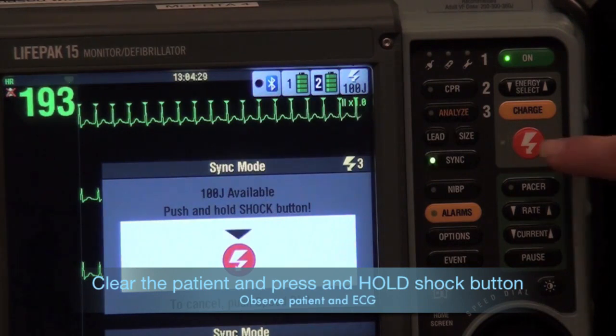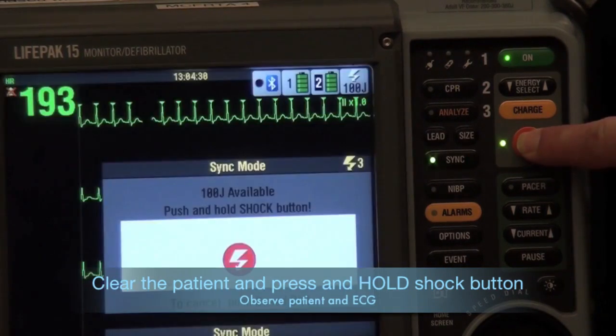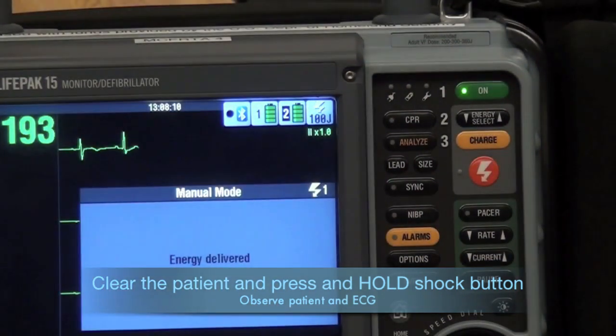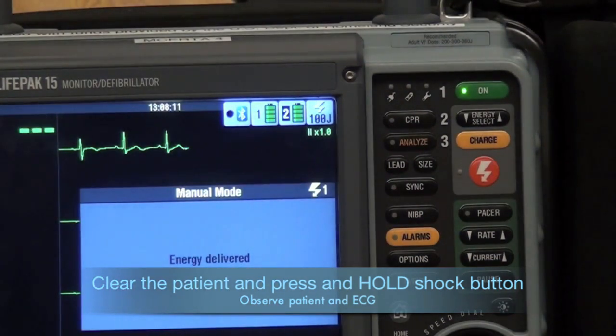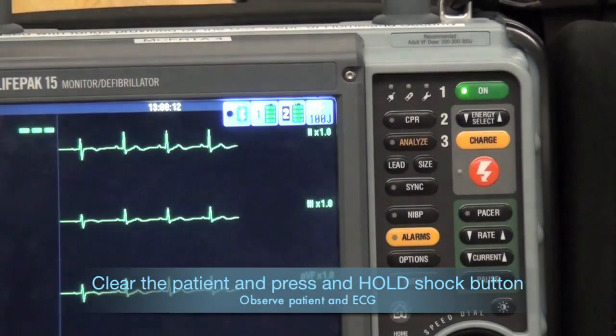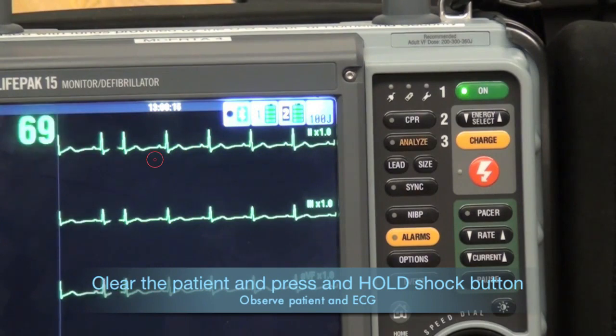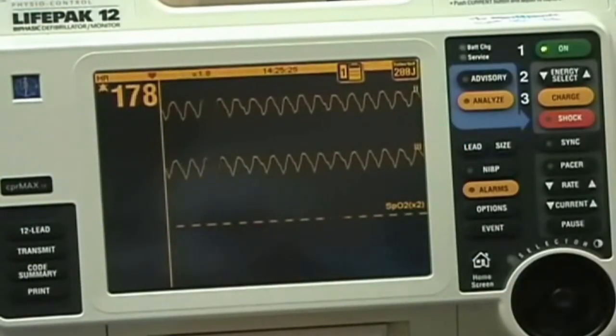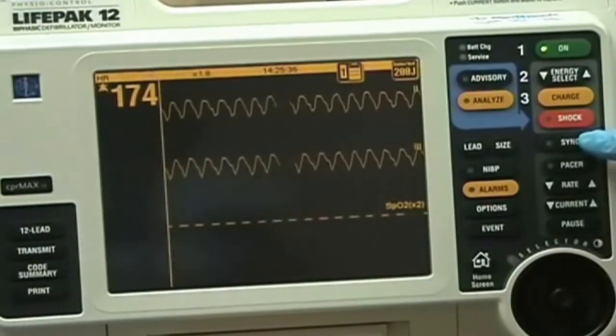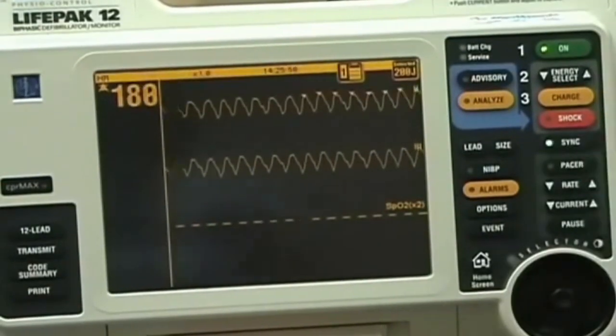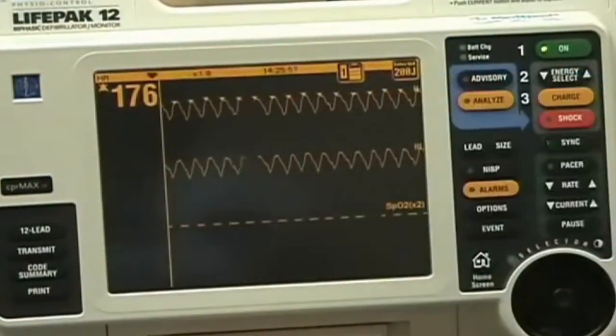Synchronization avoids the delivery of a low energy shock during cardiac repolarization — the T wave. If the shock occurs on the T wave during repolarization, there is a high likelihood that the shock can precipitate ventricular fibrillation.